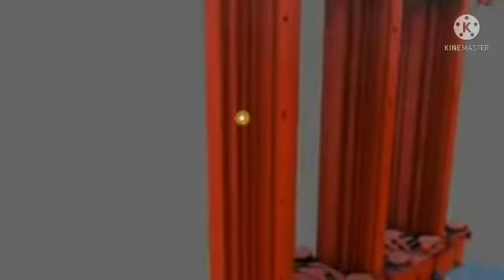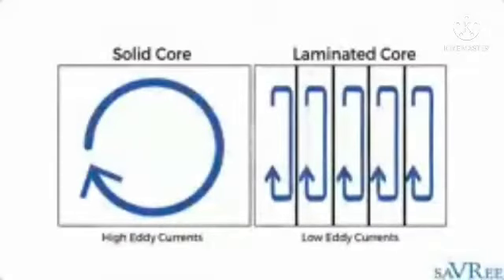You can see on the side here that we've got these straight lines. These straight lines indicate to us that the sheets are of a different geometry, and as you've clamped them together you get this wavy pattern. If we can see, I'll move over to another limb. You can also see it over here, and that's because the core is not perfectly cylindrical. Now the reason that we clamp these very thin laminate sheets together is because we want to reduce the hysteresis and the eddy current losses.